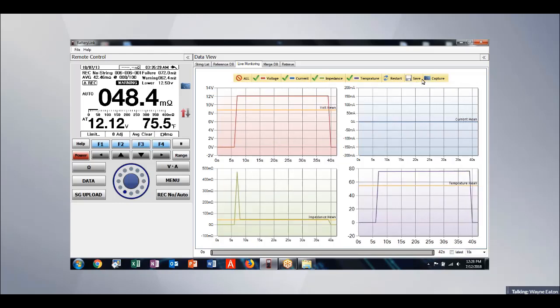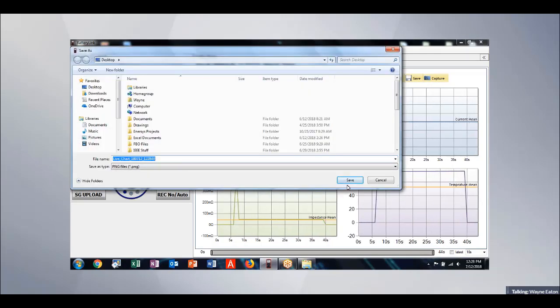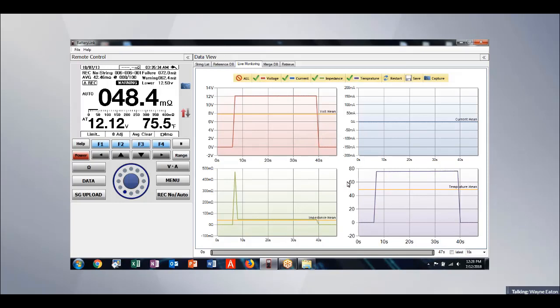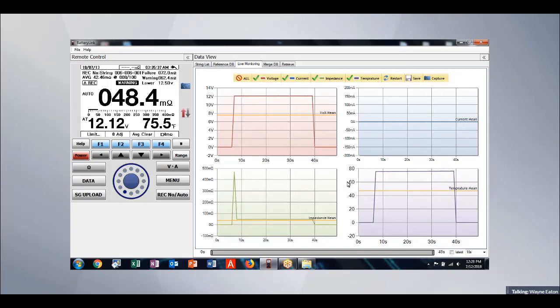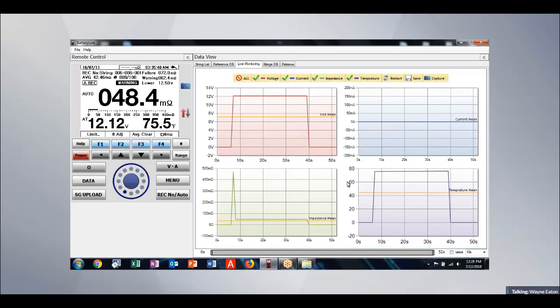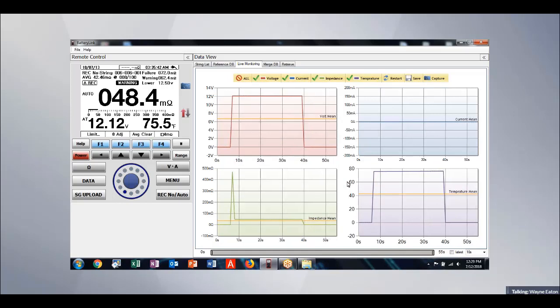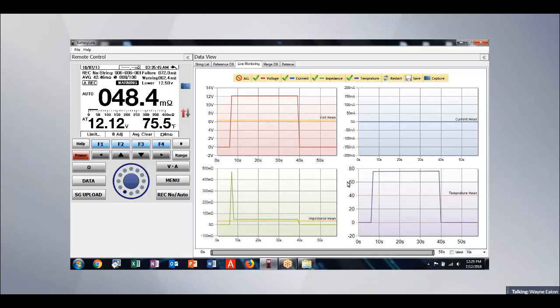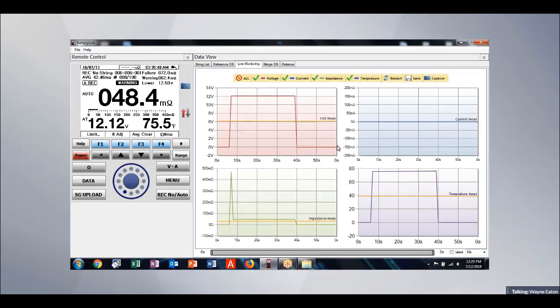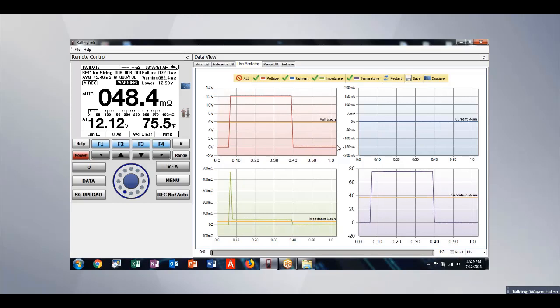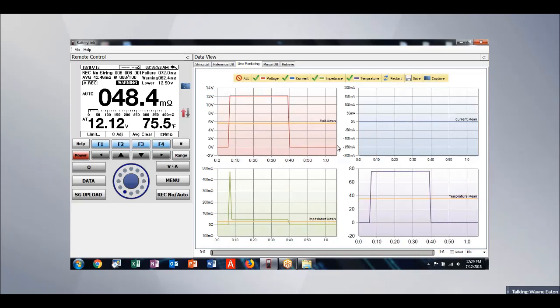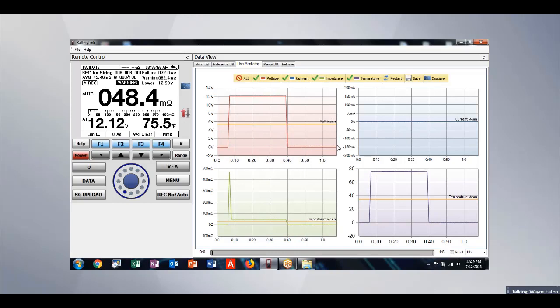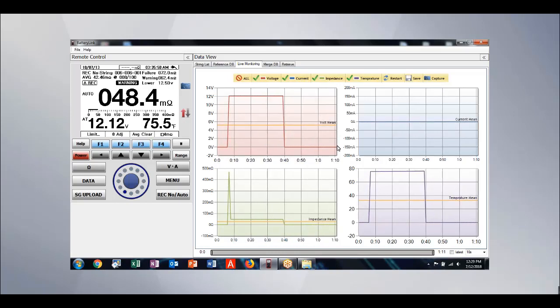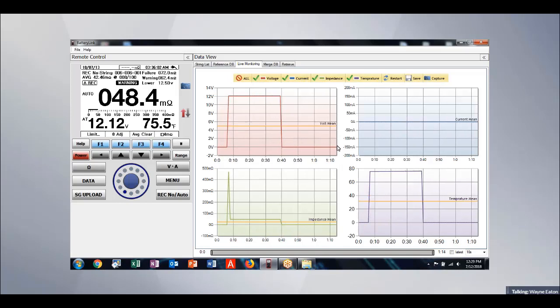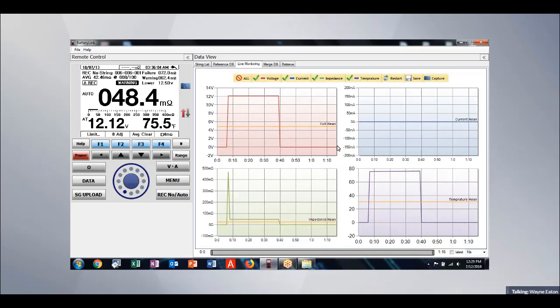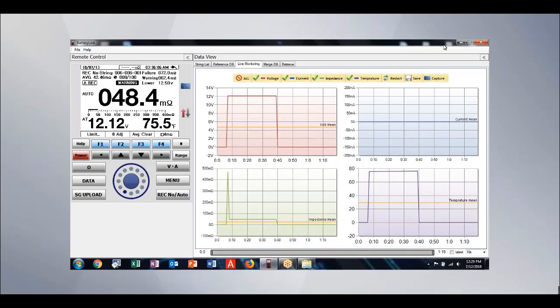And again, I can save this or do a screen capture of it out to the desktop. And then I can do that same with the known good battery, and I can make a diagnostic comparison of how a battery that comes up as warning or fail looks compared to a battery that's a known good battery. So this is an internal feature of the SBS-6500. For this feature to work, it does require that the 6500 be connected to the software on the laptop. So the live monitoring feature doesn't work on the 6500 without the laptop connection and the software.